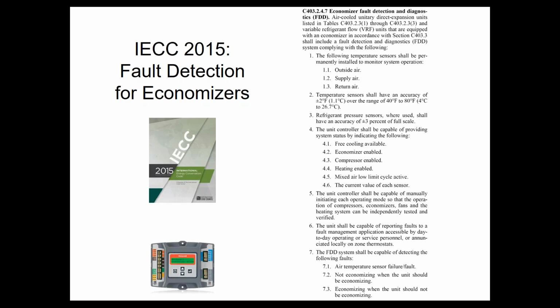So it's got to track these temperatures and try to determine if things are out of whack, try to figure out if economizer damper is not shutting all the way or if it's not opening all the way, all those sorts of things. And the Honeywell Jade Economizer, like I'm showing in the bottom corner of the screen there, it does that. I believe the Belimo Zip Economizer does that. And then a lot of your DDC type guys can do it as well.